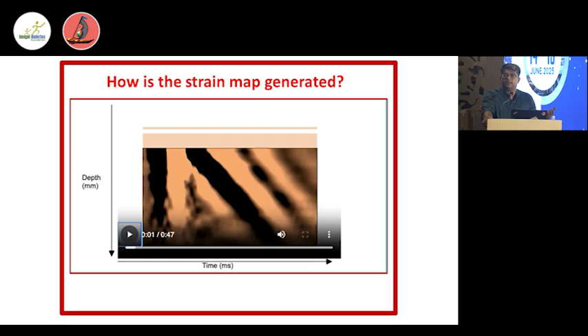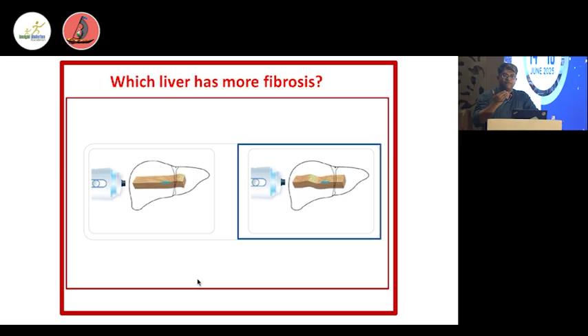So this is the exact principle of Fibroscan. What happens is the mechanical actuator creates a shear wave. It travels from here to here through the liver or any tissue. And the ultrasound cleverly measures the speed of the shear wave by measuring the displacement of the tissue. So we have the machine giving a displacement and it is measuring how far the displacement of the shear wave is moving. And by correlating it, we can find an indirect measure of the stiffness of the tissue.